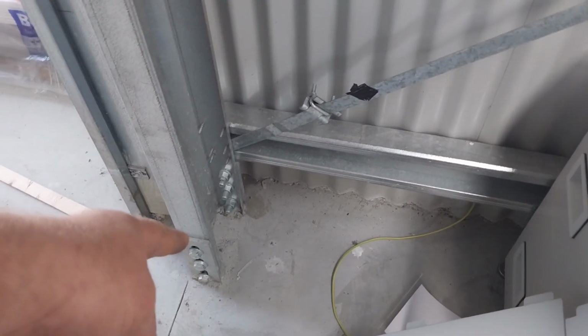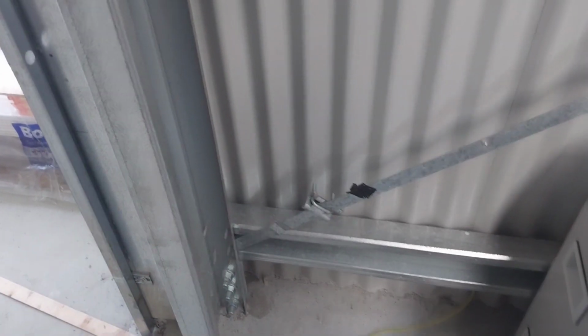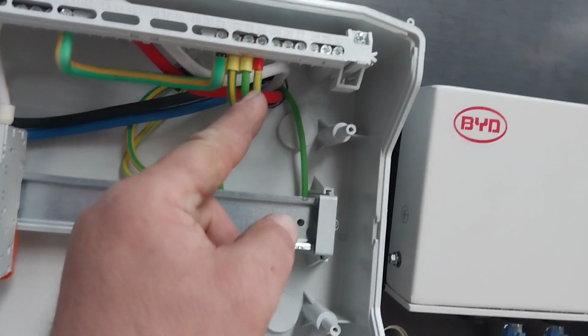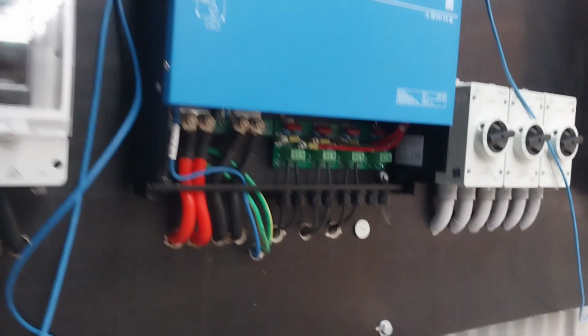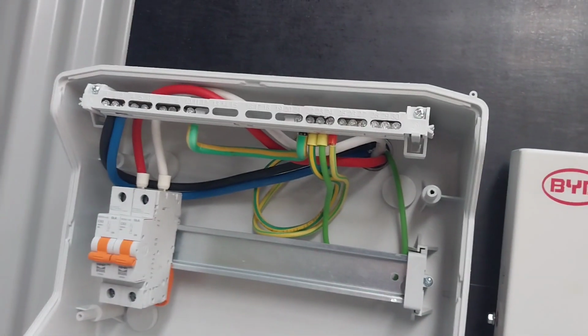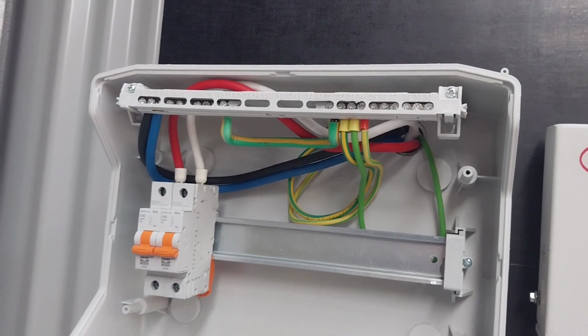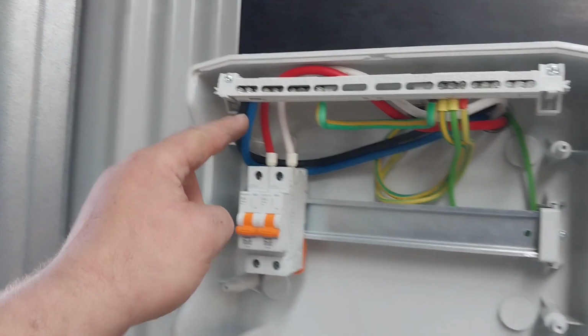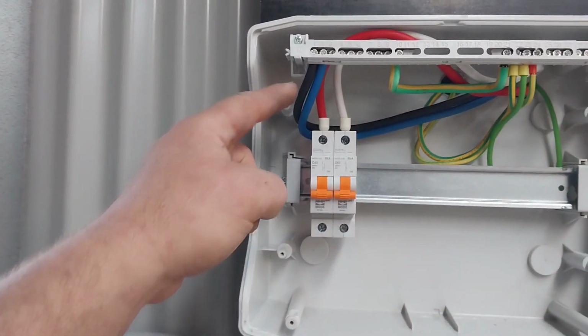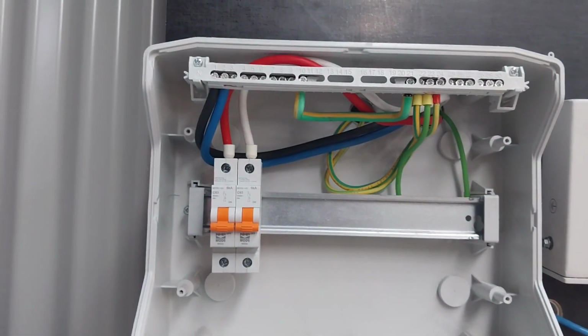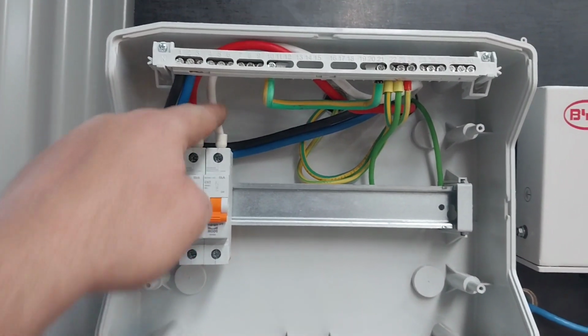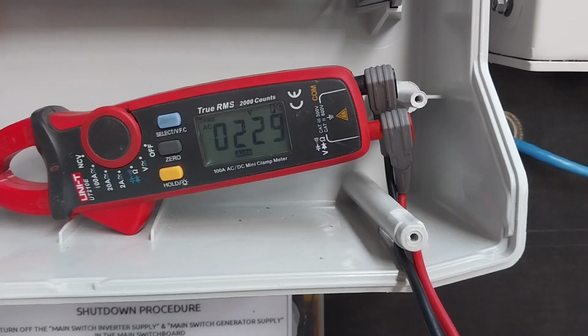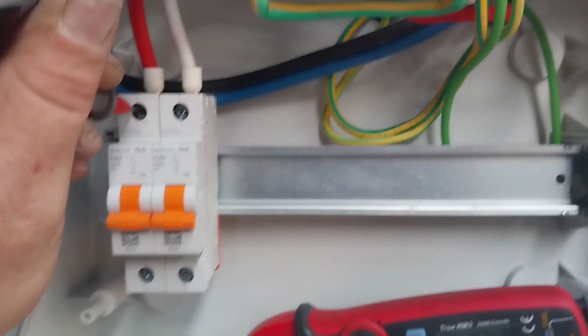Would be better off just putting an earth to the frame here, steel frame in the concrete. And the last one, of course, is the DC array. It's earthed up there on the roof. There's an MEN link to make all the safety switches go off. We've got two neutrals. One is for the normal output, and one of them's for a generator that could come later. 229 volts. That's what we want.